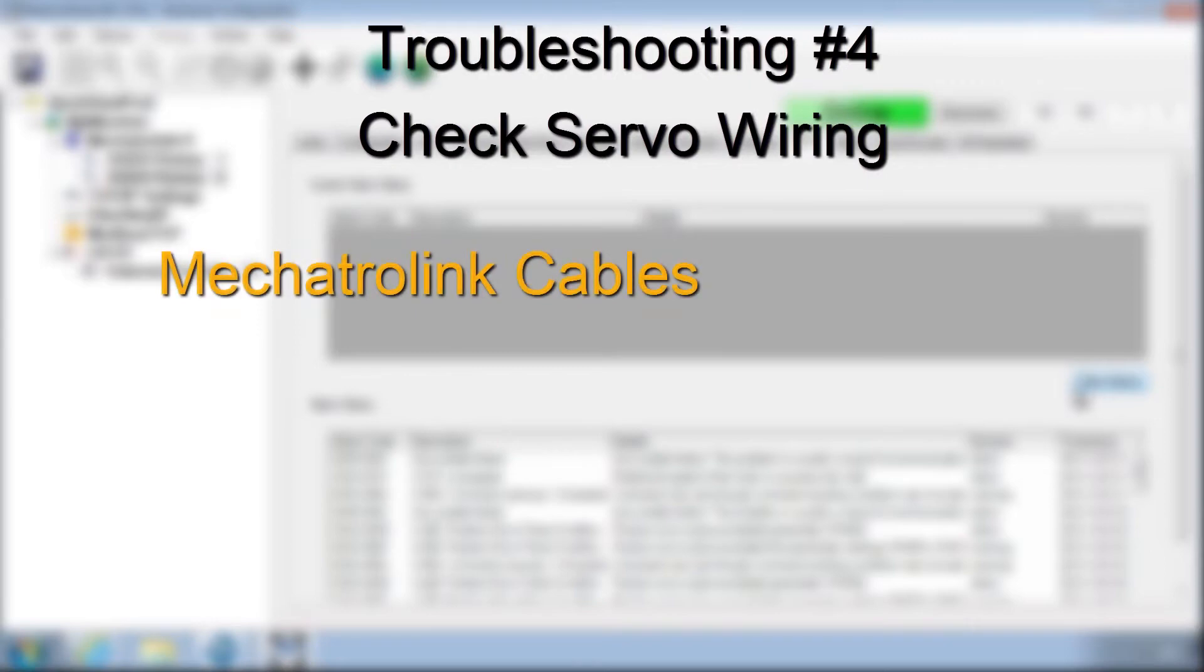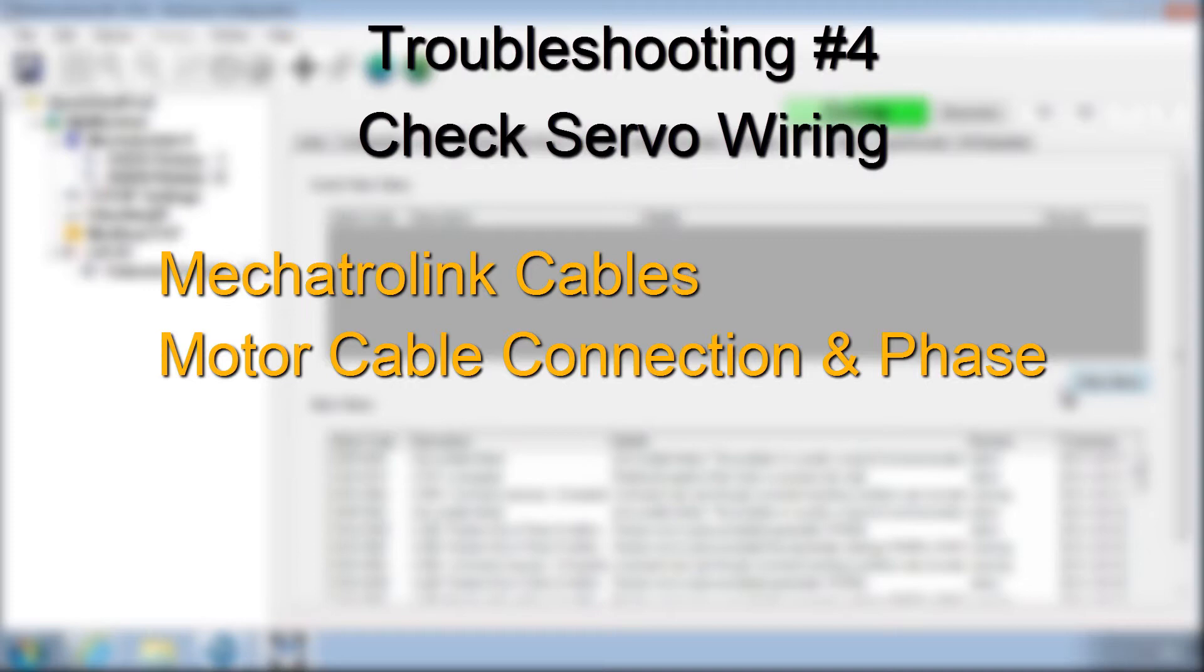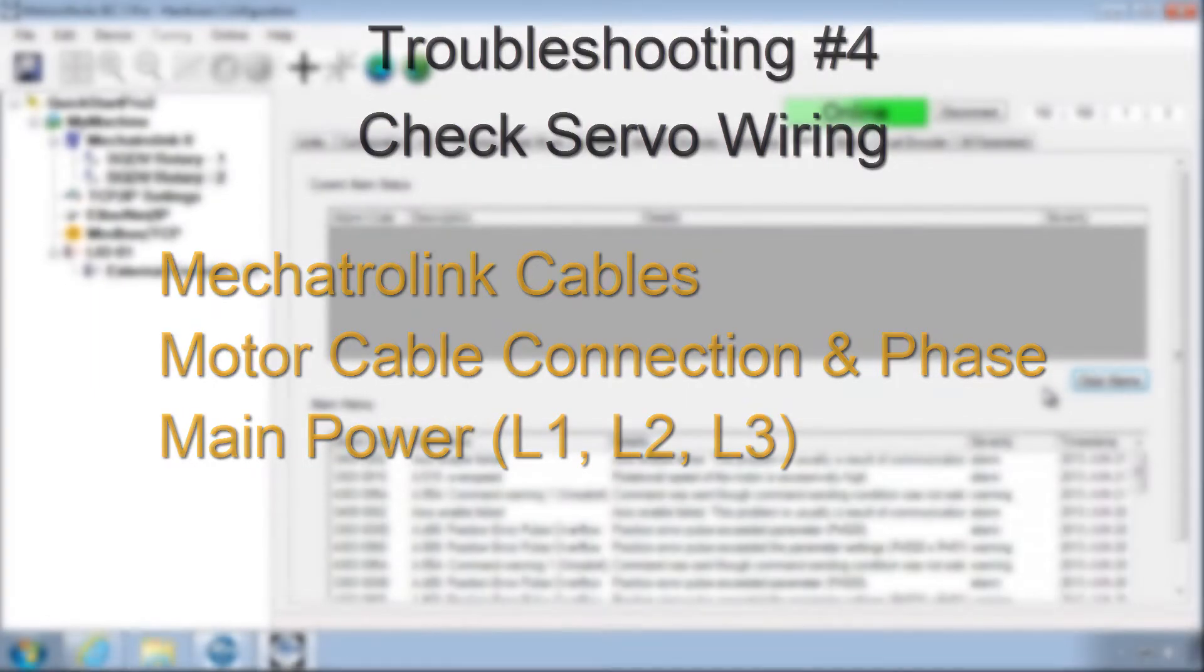Test move failure and alarm codes can be caused also by incorrect wiring, such as loose Mechatrolink cables, disconnection of the motor cable, reversal or disconnection of the motor phases U, V, and W, or disconnection of main power L1, L2, and L3 of the Sigma 5 servo amplifier.